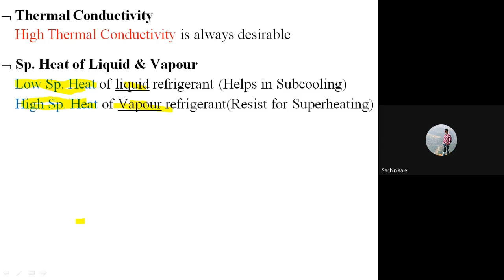Why is this so? Because low specific heat of liquid will help in subcooling, and because of subcooling we know that we are able to increase the COP of the system. And high specific heat of vapor refrigerant will resist superheating. That means that refrigerant will not easily superheat. If there is a higher degree of superheating, we know that the COP of the refrigeration system decreases. So we have to select a refrigerant which will resist superheating, and that will be resisted when the refrigerant has high specific heat of vapor.